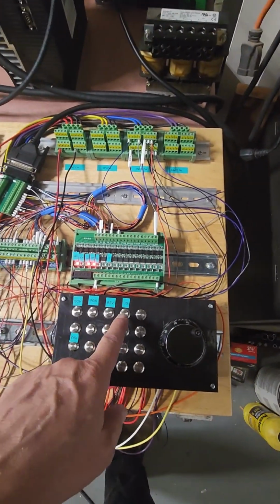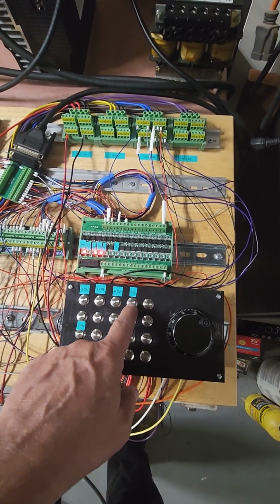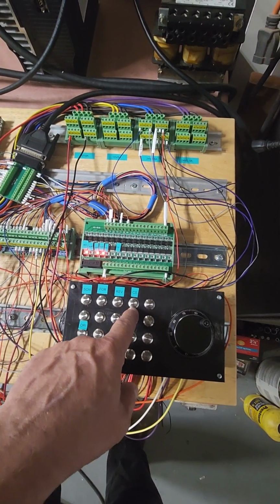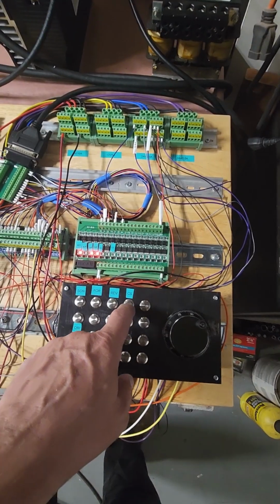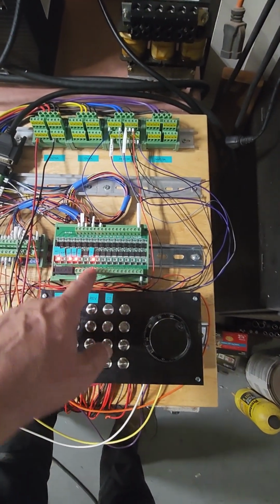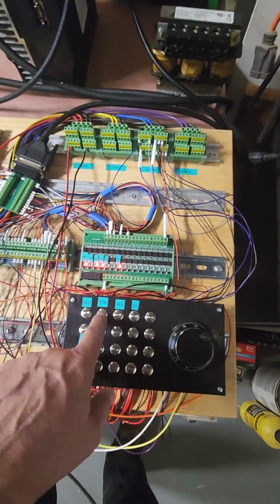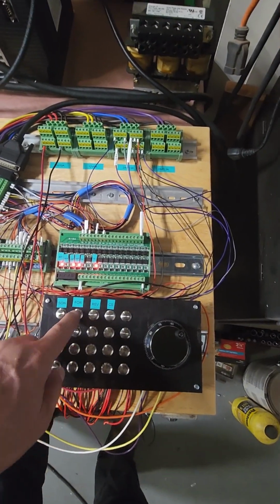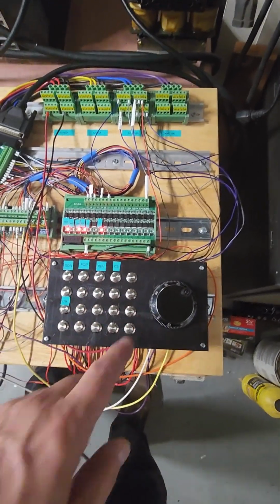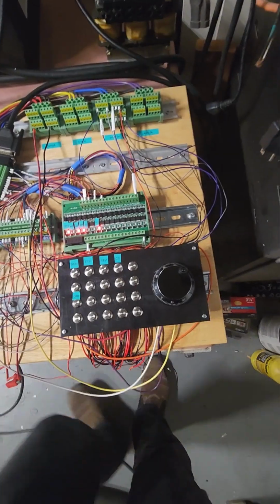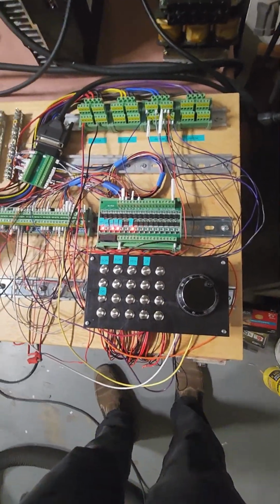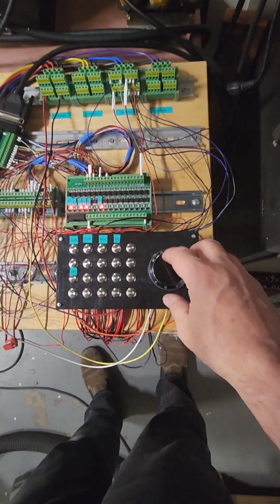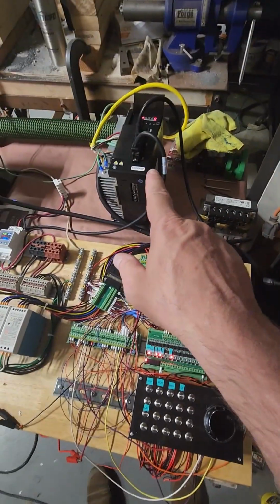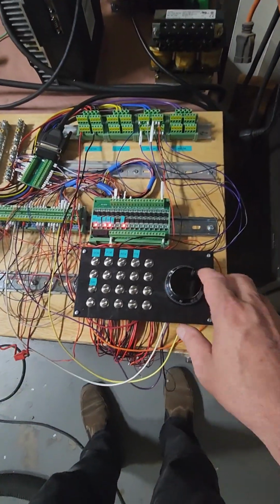And then finally I have the switching to positioning mode, where you can send pulses. When you do that, you get confirmation that these are not working anymore. I don't have signal, direction and pulse generators to test this, but I wired this encoder and changed the parameters to accept quadrature signals.